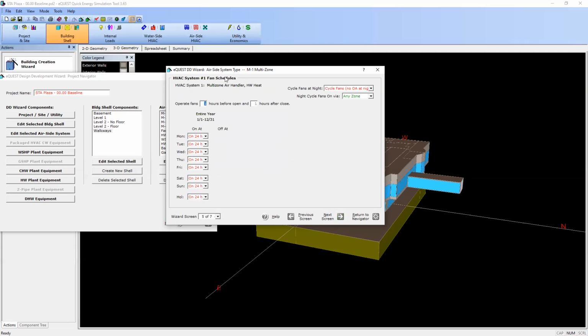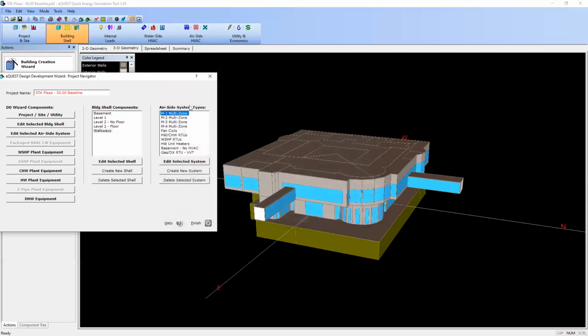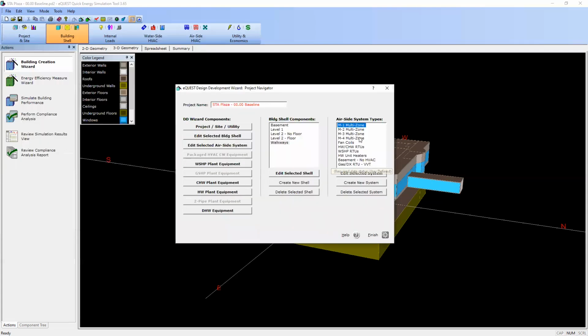And then we have the schedules. So this would be, when is the HVAC running? In this case, it's on 24 hours a day. And I create one of those for all the different system types in this building, which you can see is quite a lot. And then I can get into my chilled water and hot water plant equipment.